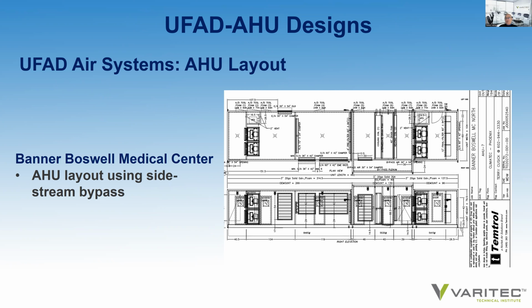A discharge air temperature sensor is mounted at the discharge of the air handler, and to maintain the supply air discharge temperature, the mixed air damper modulates open and close to allow mixed air at a higher temperature, possibly 80 to 82 degrees, into the airstream of the cooling coil downstream to provide free reheat. You want to avoid reheat at all costs because it's very expensive. This solution, however, does demand, as I covered in Psychrometrics Deconstructed Part 2, that the dehumidification of the supply air off the coil is adequate to absorb that latent gain in the mixed air, certainly in Arizona during our monsoon months.